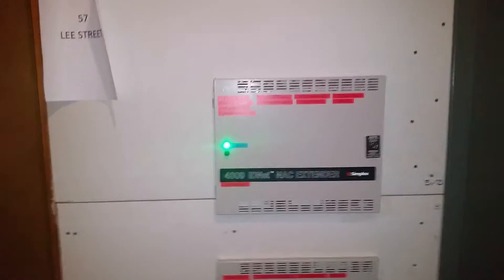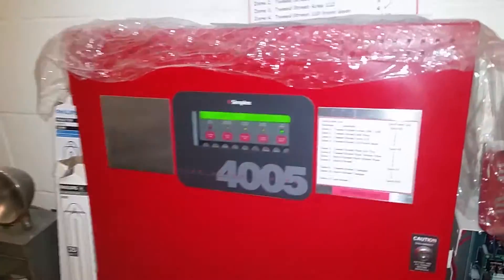We have two in this building, so I'm going to show you how they work. Let's first discuss what it is they do. They add power for horns — additional power. So many times in buildings of this size especially, the panel cannot do enough wattage. It requires more, or the panel can't provide enough loops. An array of different things.